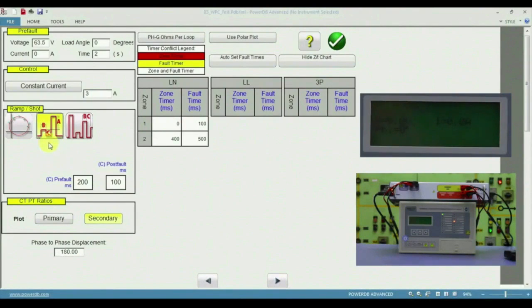So in places where you do not have sufficient time, or you want to do the relay testing in an accelerated manner, we have the third option, where we do a pulse search method. Here we have 2 points, one outside the zone and one inside the zone. So what the test kit does is it creates an impedance outside the zone. There should not be any operation. Another point inside the zone, there should be an operation.